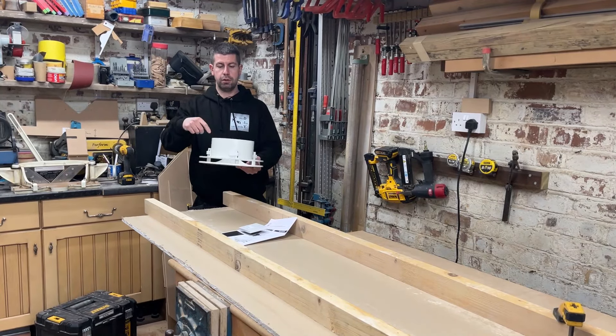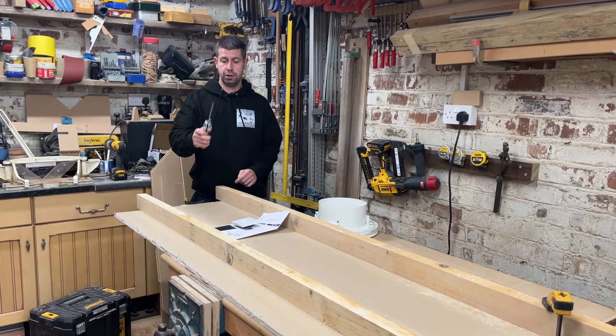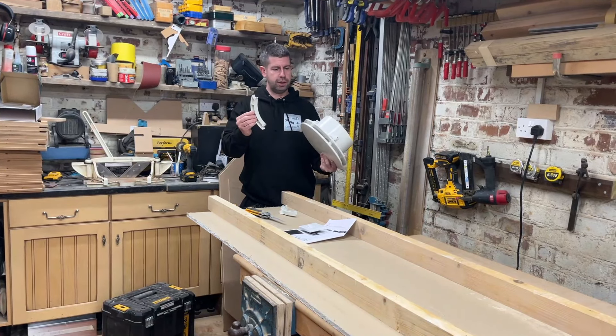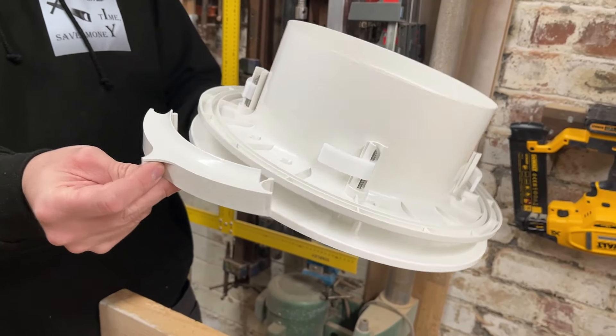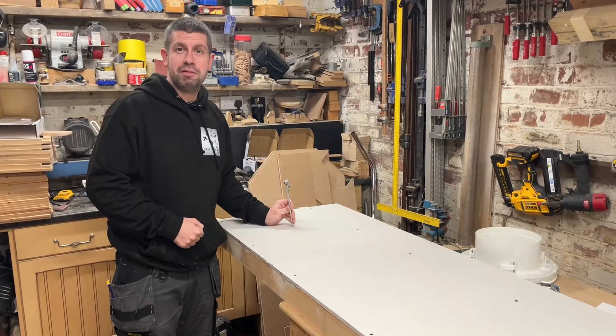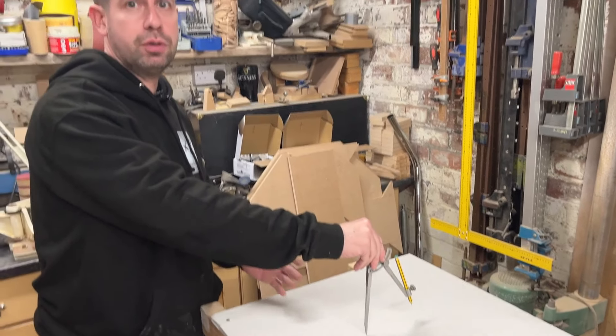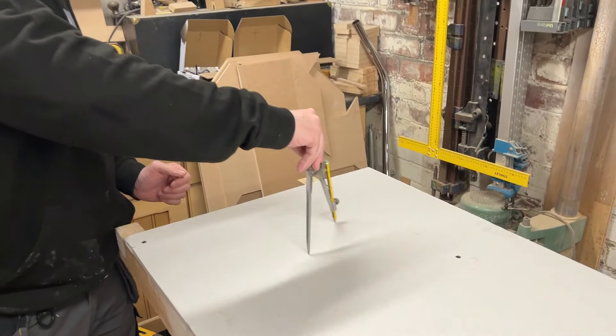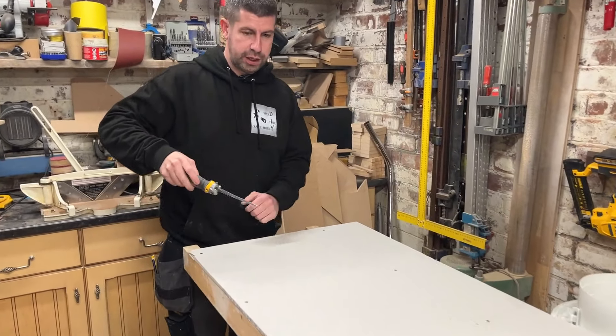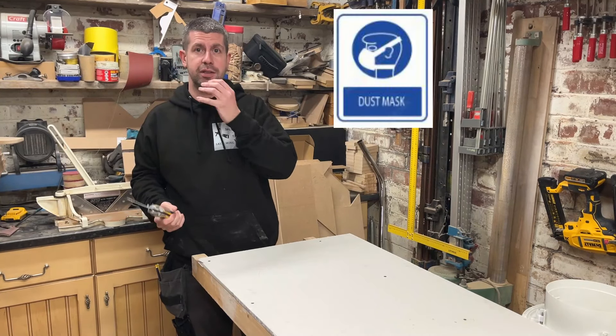The first job is to install the diffuser. It needs a round hole cutting between 240 millimeters and 260 millimeters, and the best tool for that I find is just a simple plasterboard saw. When fitting the diffuser it's best to have open space around it, but if you do have to put it close to a wall it's supplied with some little pieces that fit in there — I think that's just to stop any flow of air against the wall. Make sure to wear a mask and eye protection as there'll be dust and debris falling on you.